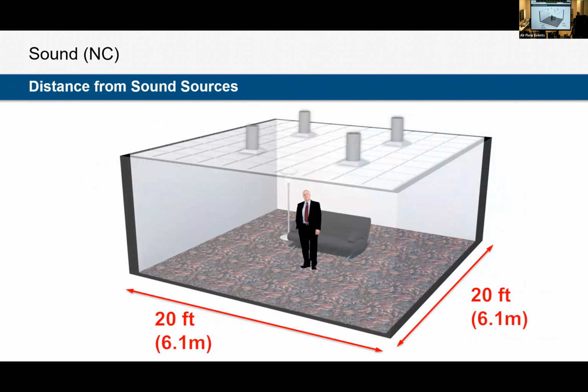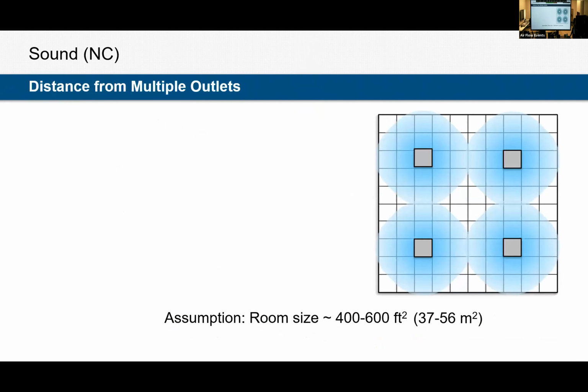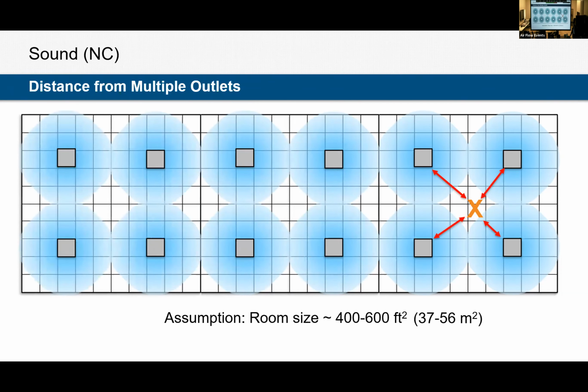And then what about distance from the sound source? We've got this kind of grumpy businessman sitting in the middle of this room. How is he going to perceive the different sound sources? We usually assume that a person can only hear sound sources within a 400 to 600 square foot room space, so our 20 by 20 room. If we've got a larger room, maybe a big open office space with diffusers all the way down to the other wall, a person might hear a little bit of the diffuser outside of that 20 by 20 space, but they are absolutely not going to hear a diffuser all the way across the room. So the diffuser right outside there is probably negligible. We're usually only concerned with the sound of our occupants within that 20 by 20 square foot space.